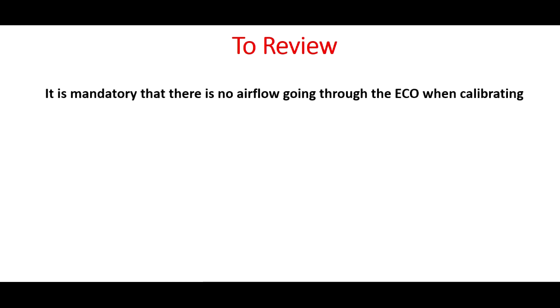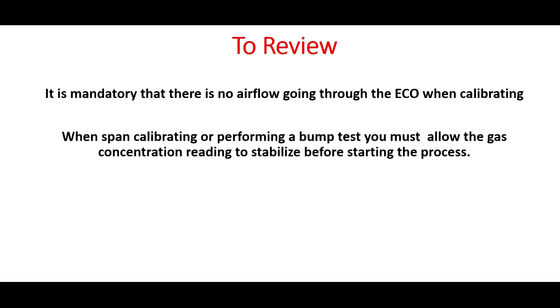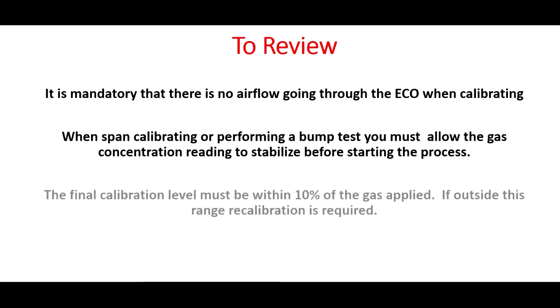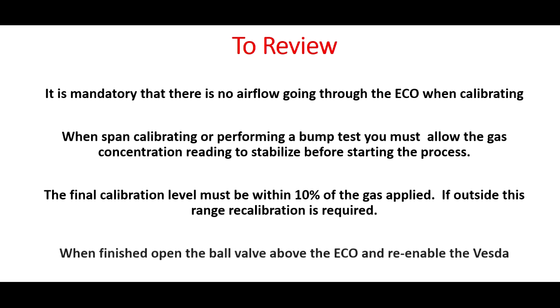To review, it is mandatory that there is no airflow going through the ECO when calibrating. When span calibrating or performing a bump test, you must allow the gas concentration reading to stabilize before starting the process. The final calibration level must be within 10% of the gas applied. If outside this range, recalibration is required. When finished, open the ball valve above the ECO and re-enable the VESDA.